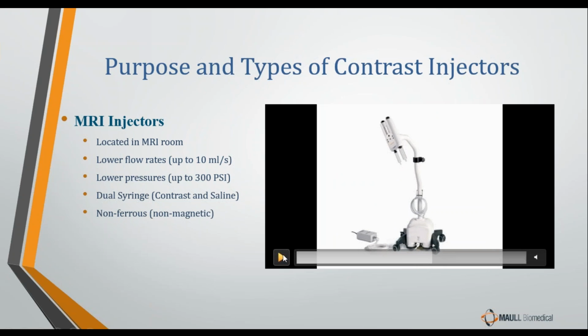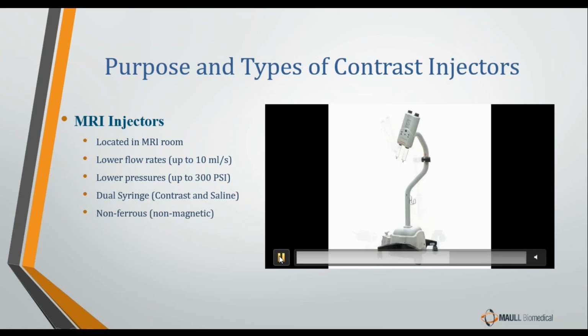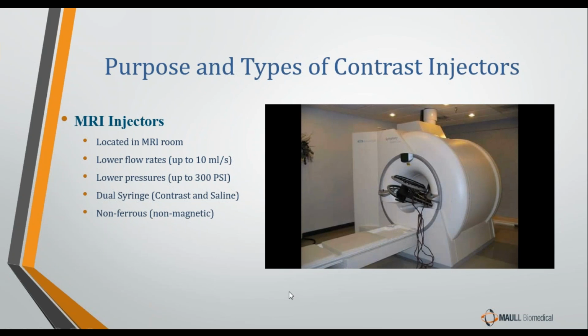Now, the biggest difference between an MRI injector and a CT injector, they both do pretty much exactly the same thing the same way, but what makes them different is that this entire pedestal here with the injector head on it is in the MRI suite with the MRI system. It is in the magnetic field. Now, due to that, this entire system has to be made of all non-ferrous or non-magnetic material. Otherwise, things like this happen.